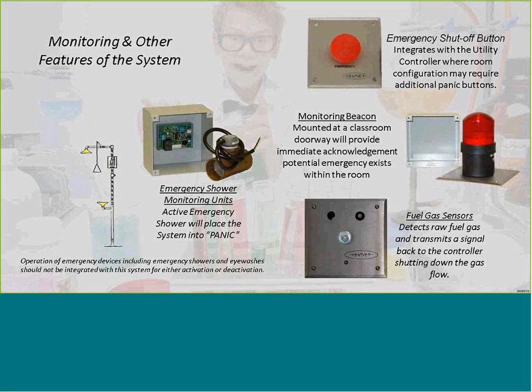All we want to do is send a signal out through the control panel to a supervisory signal back on the fire alarm, or to a monitor panel located in the principal's office or some administration area to let you know that, hey, something's going on in this room, we need to get down there right away. And when they see the water flowing, of course, they'll be able to shut the system down by pushing the arms back up or shutting off the eye wash valve itself.